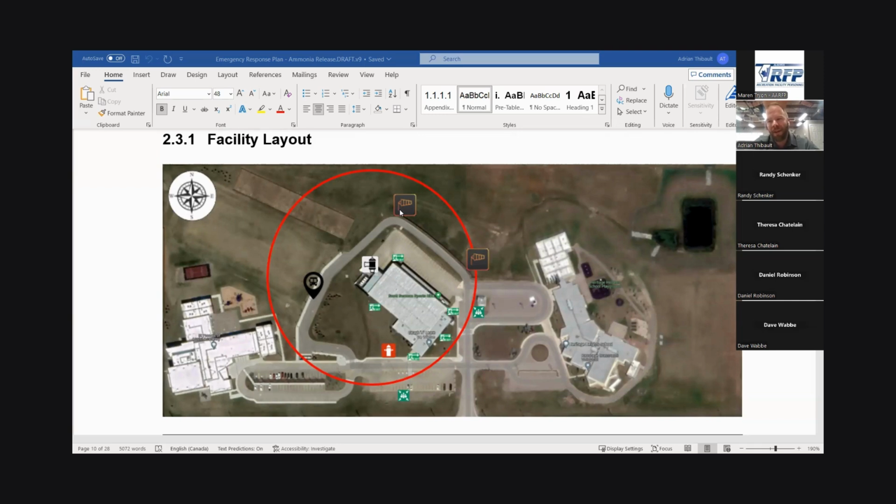What's important about the windsock, I'm sure a lot of people know, but I'm going to say it, is that there's a good chance you're evacuating all of this ammonia, whether in the room or out the stack, which should be out of the building, 10 feet above any of the building threshold, so your roof and then 10 feet above that. Good chance it's going outside. Ammonia is a natural product, and unless it's humid, it's going to want to disperse. If it's humid, it's going to stay in the cloud.